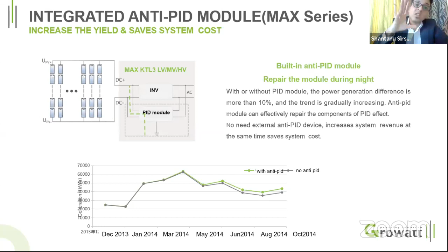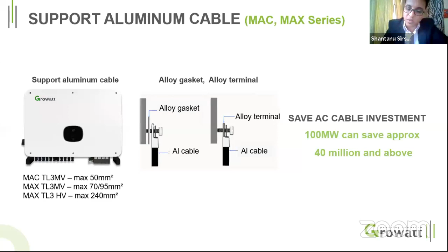We are supporting aluminum cable for our AC side. For the Max series, up to 70 and 95 square mm cable can be used for 400 volts, and for 1500 volts you can go up to 240 square mm cable. You can also implement a Y connector.